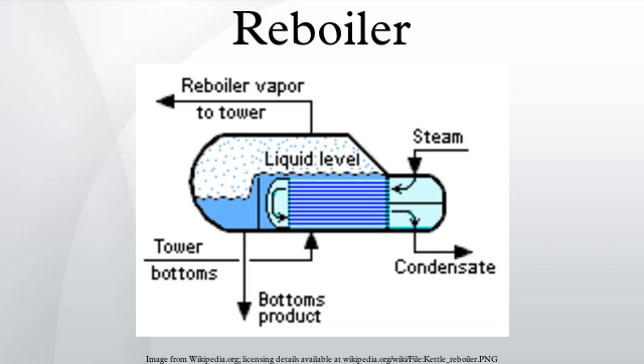Kettle Reboilers: Kettle reboilers are very simple and reliable. They may require pumping of the column bottom's liquid into the kettle, or there may be sufficient liquid head to deliver the liquid into the reboiler. In this reboiler type, steam flows through the tube bundle and exits as condensate. The liquid from the bottom of the tower, commonly called the bottoms, flows through the shell side. There is a retaining wall or overflow weir separating the tube bundle from the reboiler section where the residual reboiled liquid is withdrawn, so that the tube bundle is kept covered with liquid and to reduce the amount of low-boiling compounds in the bottoms product.